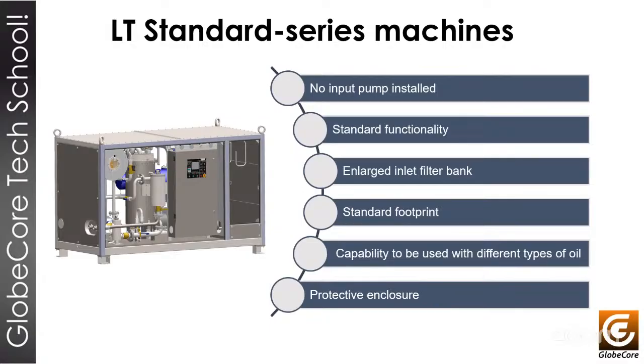Due to no input pump being installed, we have managed to make the machine more energy efficient, which is particularly evident during maintenance activity on a great number of transformers. We will save energy, we will save time with that. At the same time, the capacity of the machine is not affected with no input pump installed. The inlet filter bank has been enlarged to accelerate pumping of oil into the machine, with a greater amount of contaminants captured and prevented from entering the heating system at the vacuum chamber.